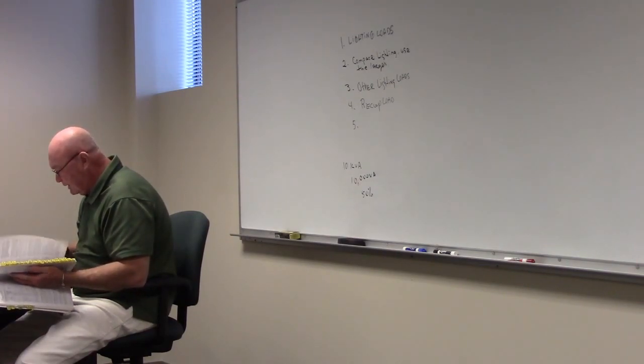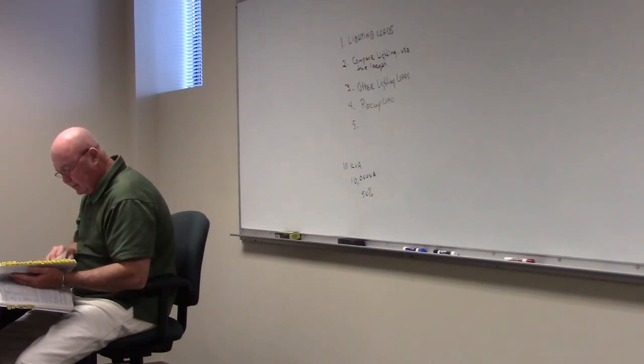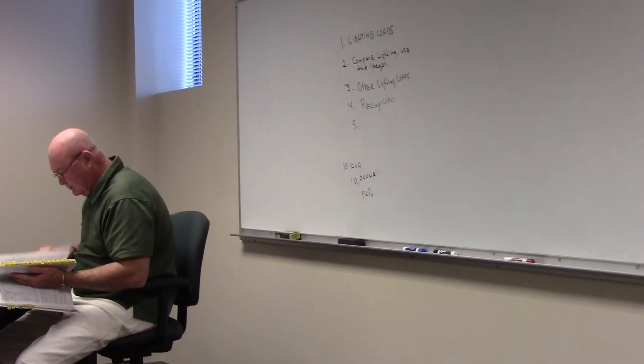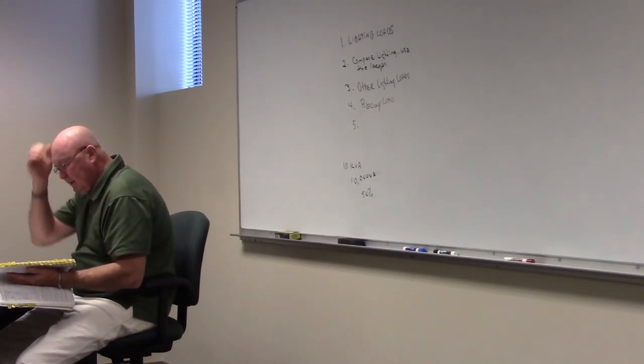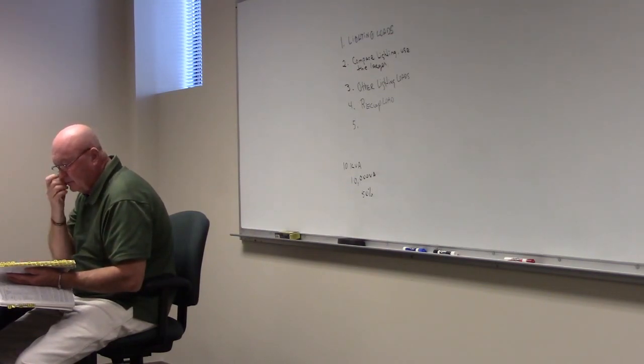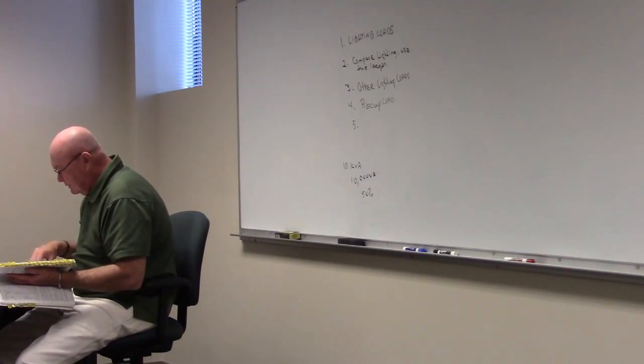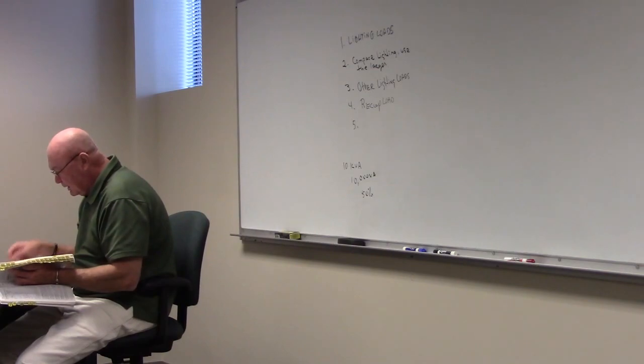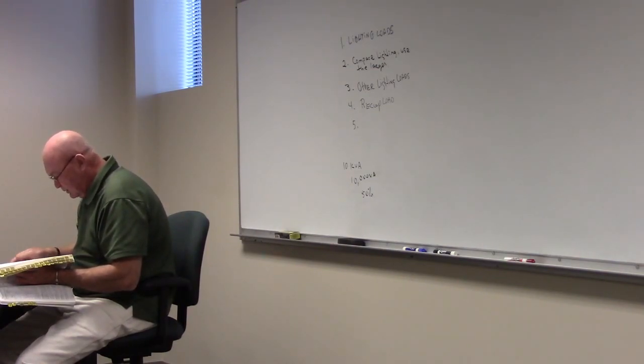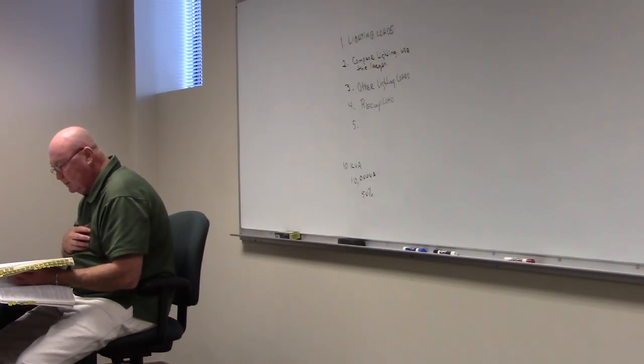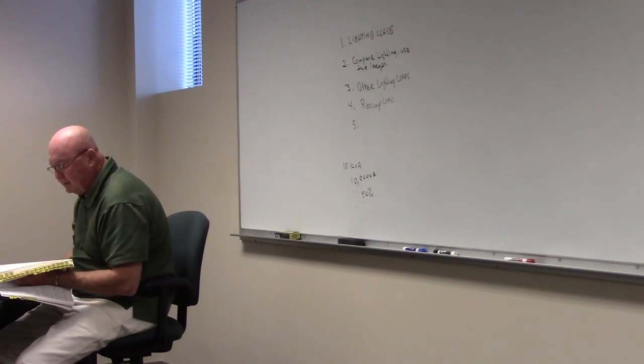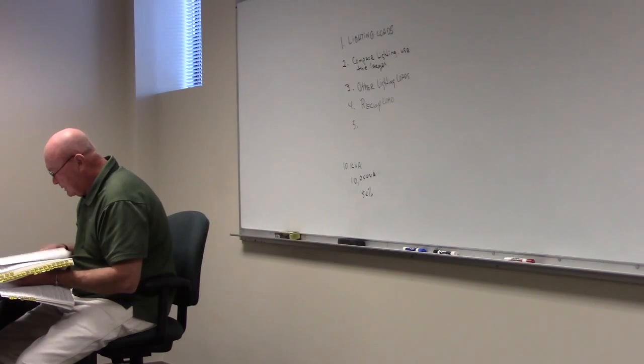All right, while we're back, let's go to 620, and it talks about the elevators. Again, are all the elevators going to run at one time? More than likely not. And so 620.14 is the demand factor for elevators. 630 is electric welders. Demand factor. Multiplier, duty cycle. With electric welders, we get into duty cycles and multipliers that we use for both of those. There are 2 tables in there. Article 660 is X-ray equipment.